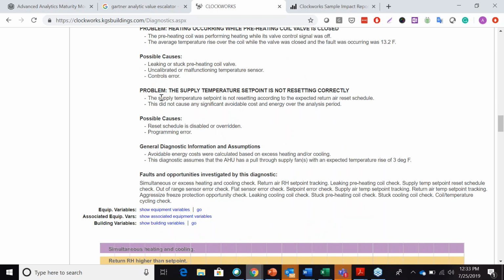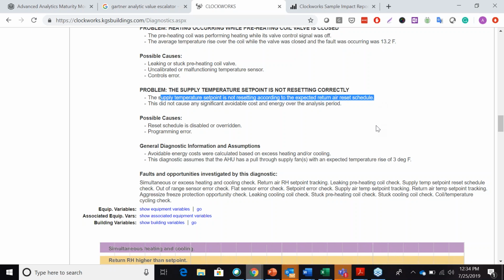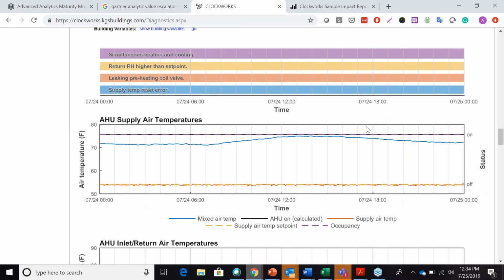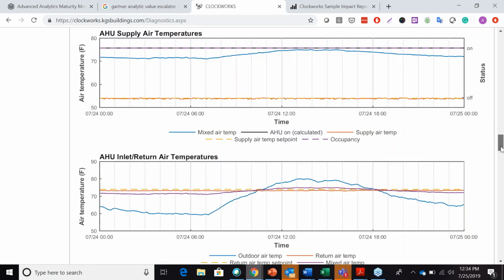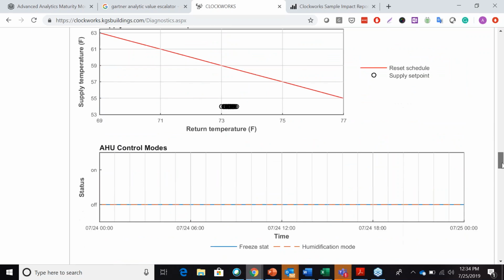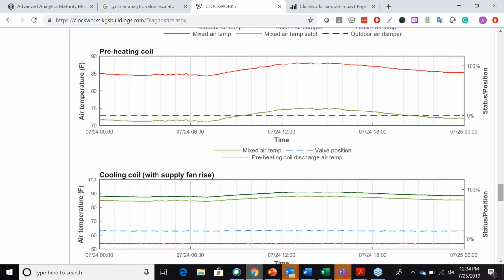And then that our reset is not being followed. So we had a return air reset schedule that's not being followed. And then again, below all of the trended information. So at the top here, when were these problems occurring? In this case, 24/7. And then a lot of trend data for those that are used to looking at information and want to sink their teeth into what's happening here. So I'm just going to jump to the coils themselves real quick and just illustrate that.